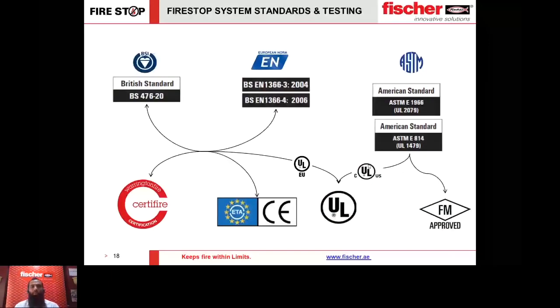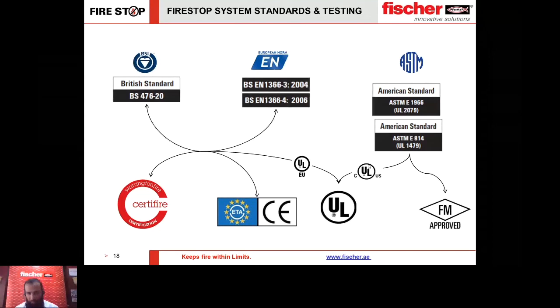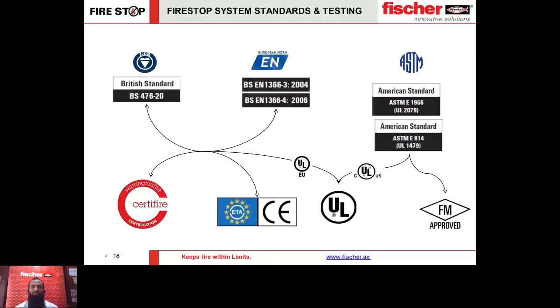The next topic covers systems, standards, and testing. All firestop applications have to be tested. The rating is always related to the barrier — somebody constructs a two-hour rated barrier, an MEP pipe makes a hole, and the rating becomes zero. When we want to reinstate that we use fire stopping, and fire stopping has to be tested. This is related to fire, so we cannot do a simple mathematical calculation to determine thickness — it has to be tested.